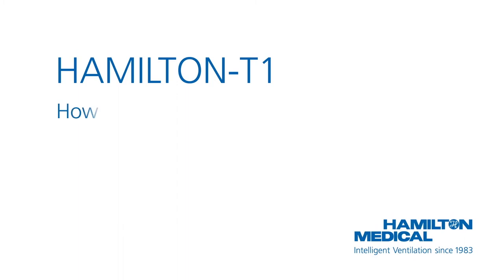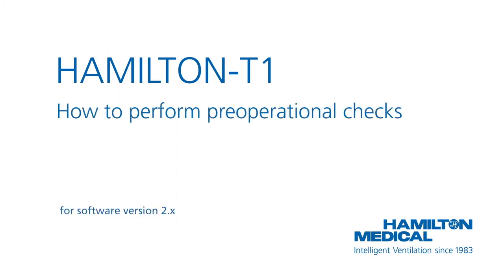This how-to video will show you how to perform the pre-operational checks, including calibration of the flow sensor and a breathing circuit tightness test. You'll also learn how to calibrate the O2 sensor and zero calibrate the CO2 sensor if this option is available. Although we are using a Hamilton T1 in this video, all the procedures we demonstrate here are the same for Hamilton C1 and Hamilton MR1 ventilators.